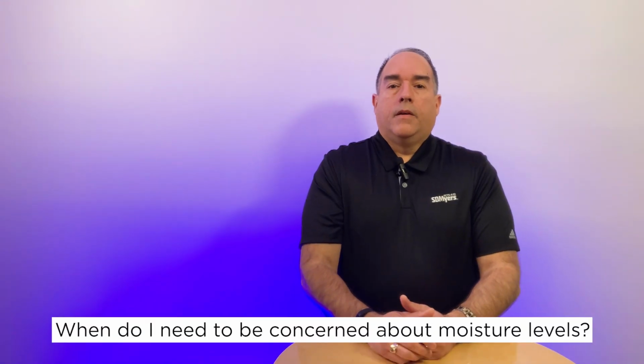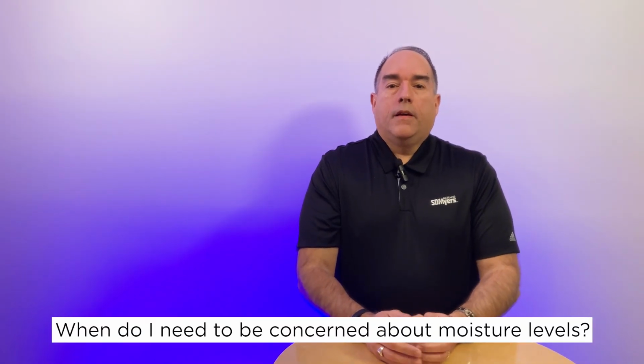So when do I need to be concerned about moisture levels in my transformer? Since moisture can be tolerated at different levels based on voltage class, it really depends on the size and rating of the transformers. SDMyers criteria is based on limits stated in the IEEE standards.